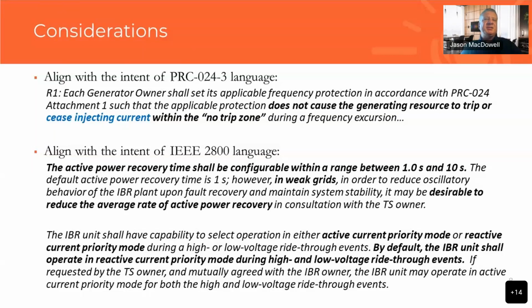It also acknowledges that there are a couple of different priorities, active power priority and reactive power priority, that have to be demonstrated. By default, the IBR should operate in a reactive power priority mode for both low and high voltage disturbance events. If for any reason active power priority is needed, that would be coordinated with the transmission system owner operator. But by and large, for the vast majority of systems around the world that need reactive power support and voltage support both during and after an event, reactive power priority is a very preferred and very effective means for riding through and recovering from faults and making sure we can support localized voltage and avoid interactions.